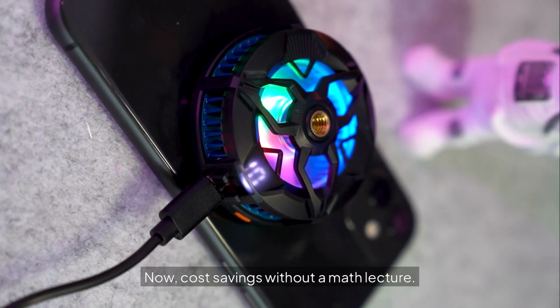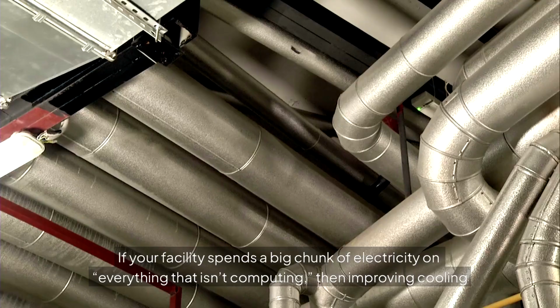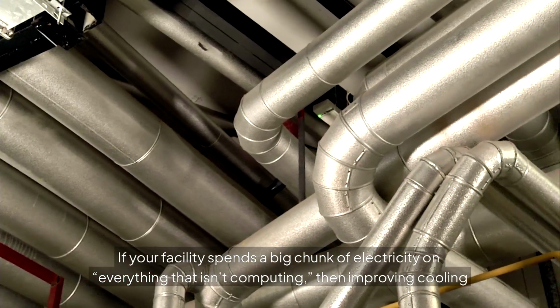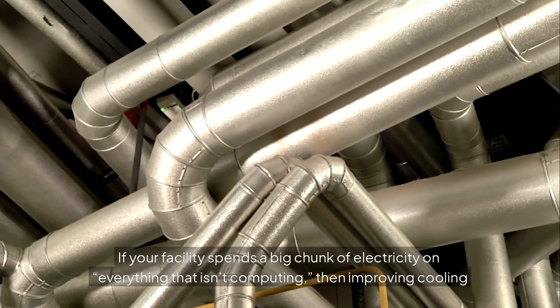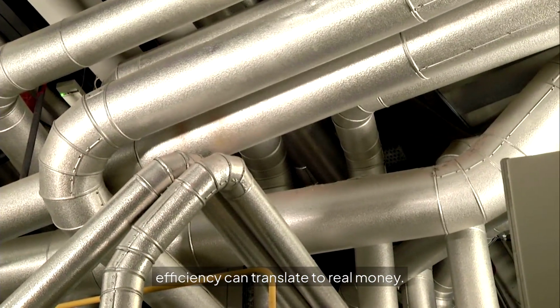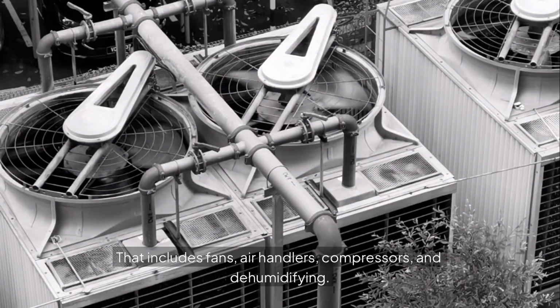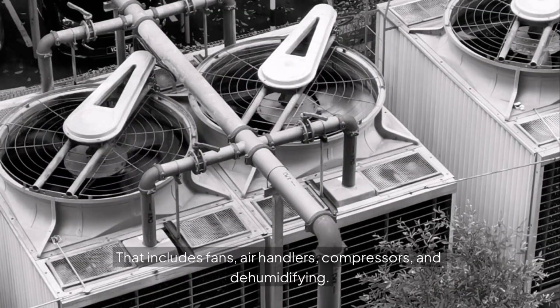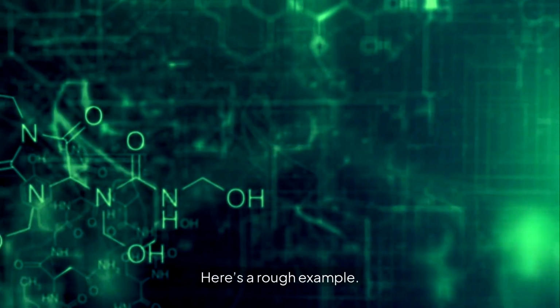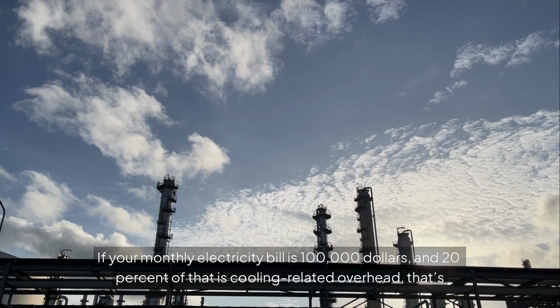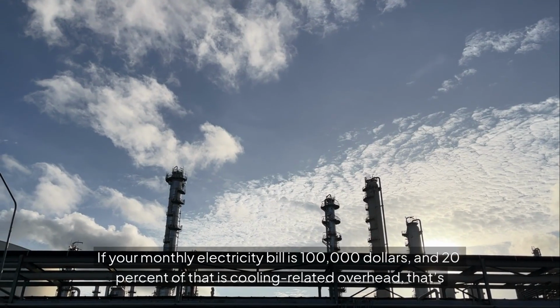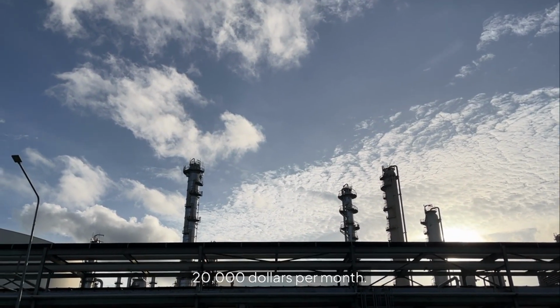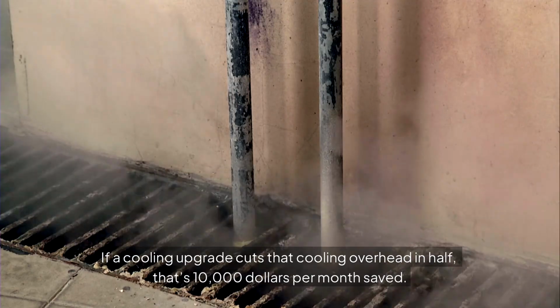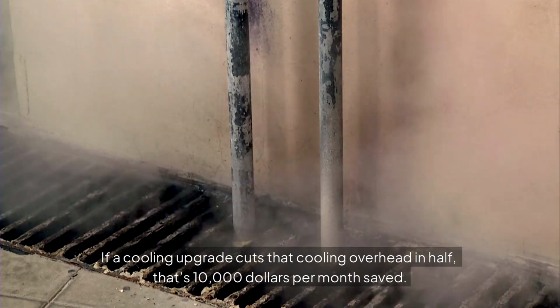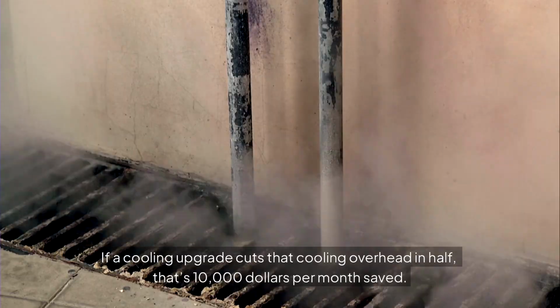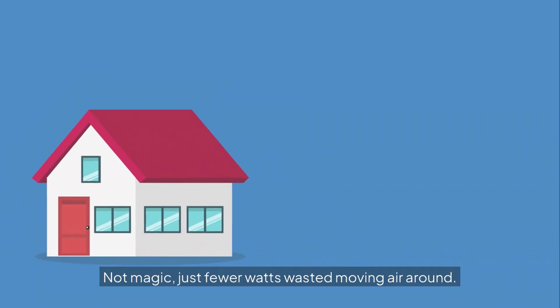Now, cost savings without a math lecture. If your facility spends a big chunk of electricity on everything that isn't computing, then improving cooling efficiency can translate to real money. That includes fans, air handlers, compressors, and dehumidifying. Here's a rough example: if your monthly electricity bill is $100,000 and 20% of that is cooling-related overhead, that's $20,000 per month. If a cooling upgrade cuts that cooling overhead in half, that's $10,000 per month saved. Not magic, just fewer watts wasted moving air around.